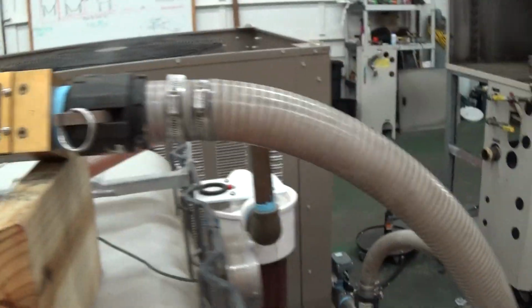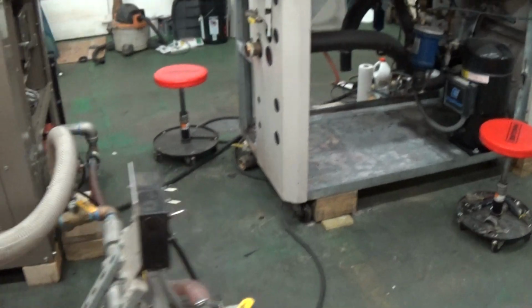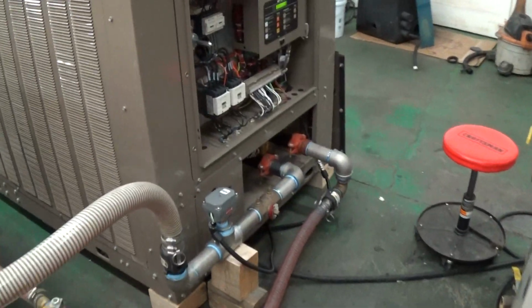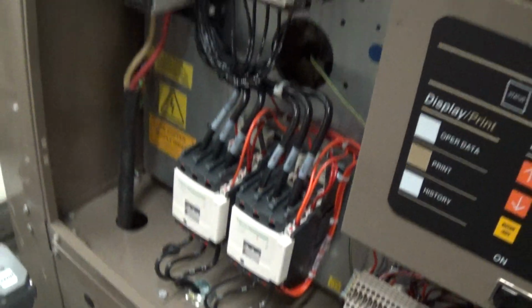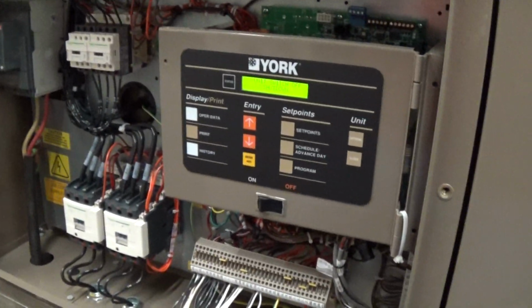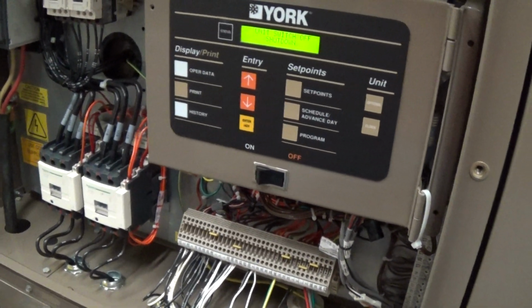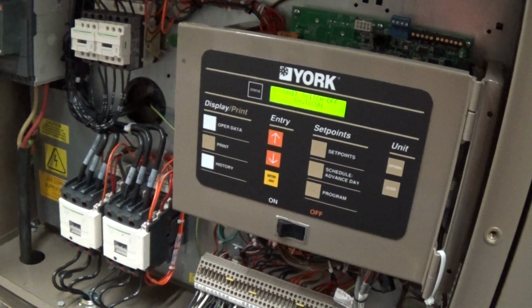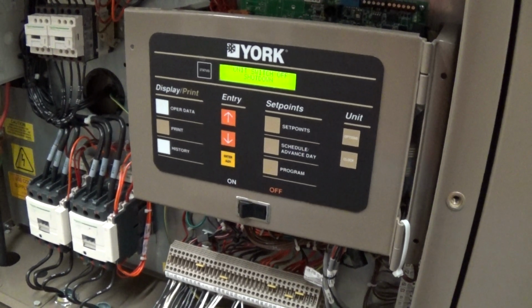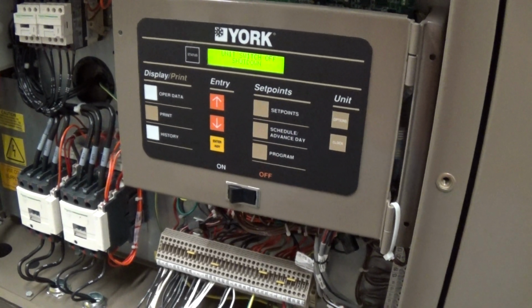At standard temperatures, that's about... actually, you'll want to see a little bit more than that at standard temperatures. But for glycol, like 25F, what we're going to do today, when you take into consideration the derating of a glycol low temperature application, that 50 or 60 GPM is actually ideal.